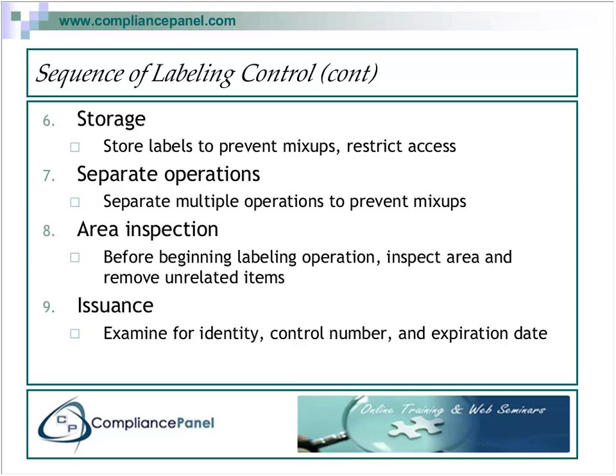Area inspection is a critical area, if you will, when it comes to label control. Before a labeling operation is begun, each area must be inspected and any unrelated items, any previous labels, any previously rejected labels have to be removed to avoid possible inconsistencies. Line clearance is the term that's often used for this.